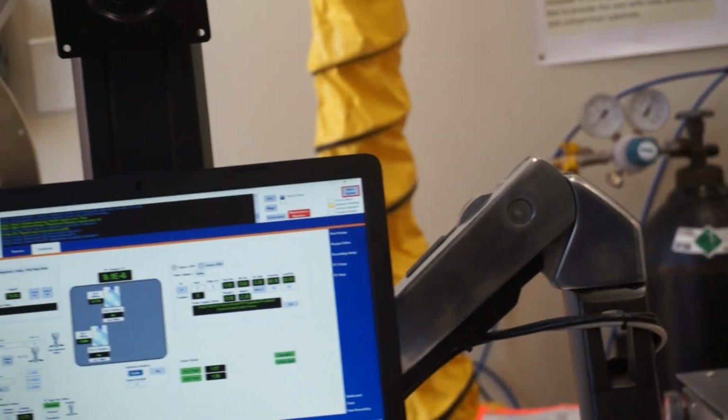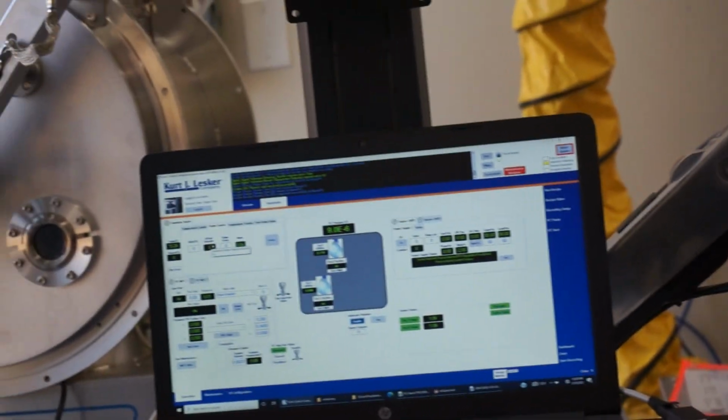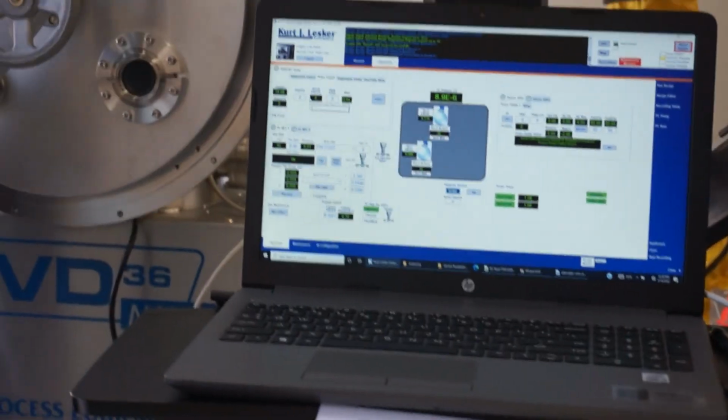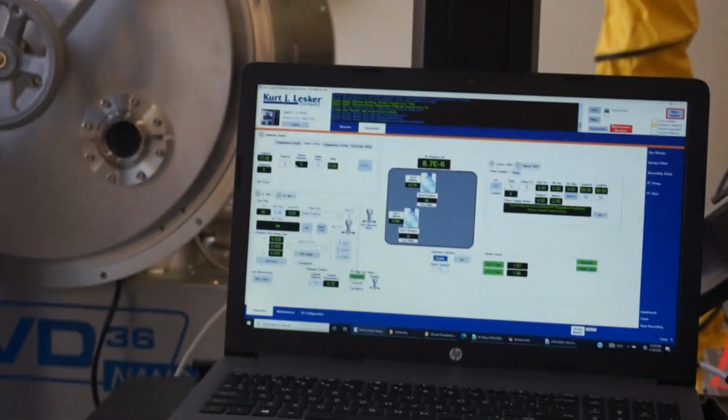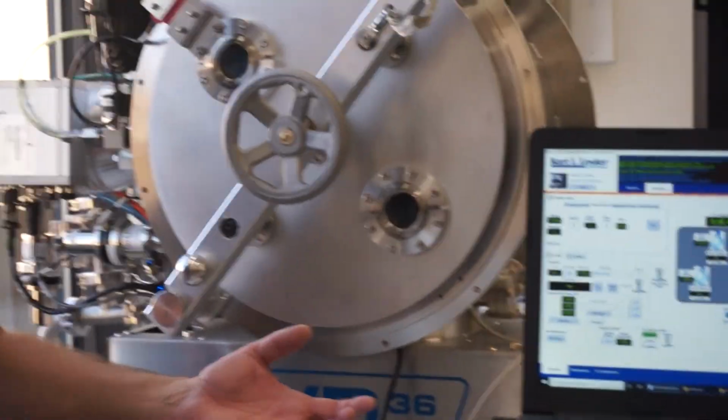Alright, so substrate heater, power control. I don't typically use power. Power control is kind of like the flow mode in the MFCs. You just put a % power in, it just takes off. And if you put 15% power in, whatever temperature you achieve, that's what you get.